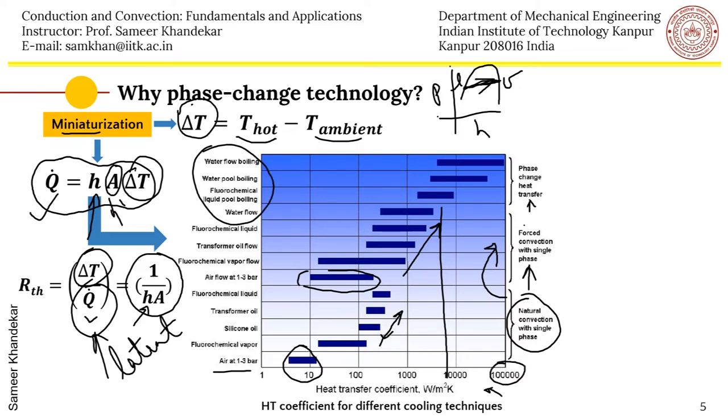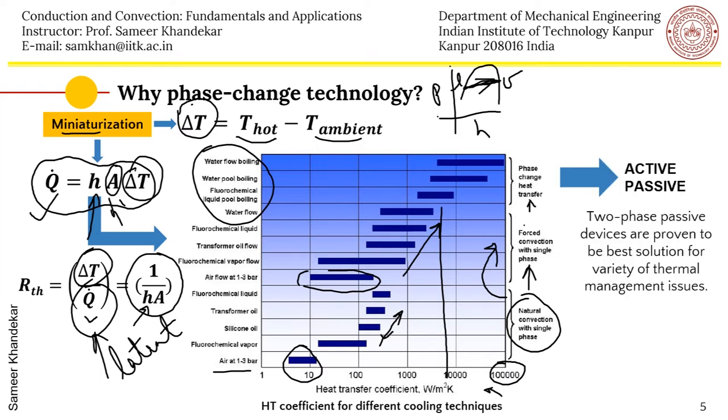So you can have active two-phase systems like flow boiling, or you can have passive two-phase systems. In this lecture we will of course concentrate on passive two-phase systems, because they are proven to be the best solutions for a variety of thermal management issues. They are passive, they have very large heat transfer coefficients, they make use of the latent heat, and there is no external pump required to run these systems.